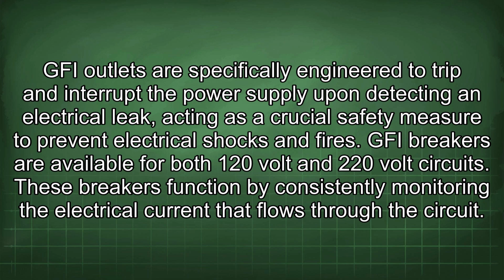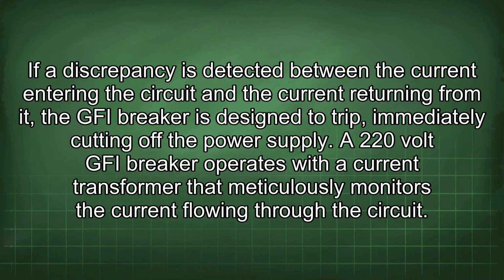GFI breakers are available for both 120-volt and 220-volt circuits. These breakers function by consistently monitoring the electrical current that flows through the circuit. If a discrepancy is detected between the current entering the circuit and the current returning from it, the GFI breaker is designed to trip, immediately cutting off the power supply.